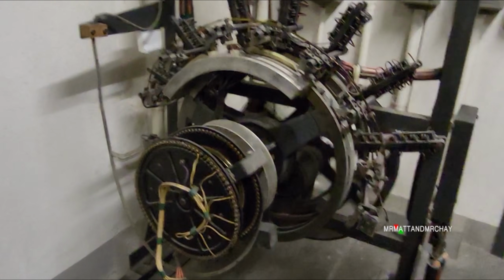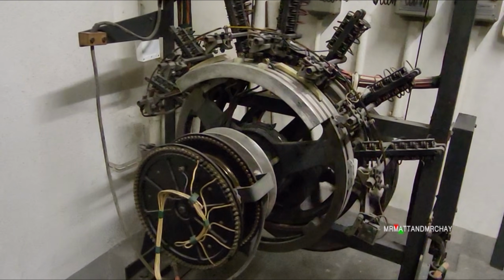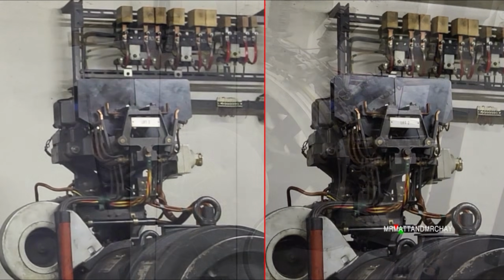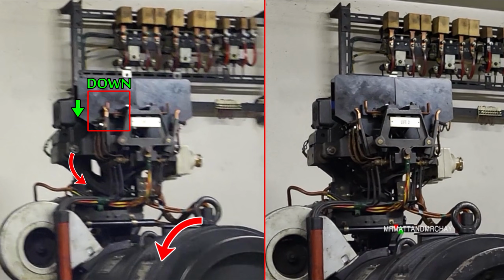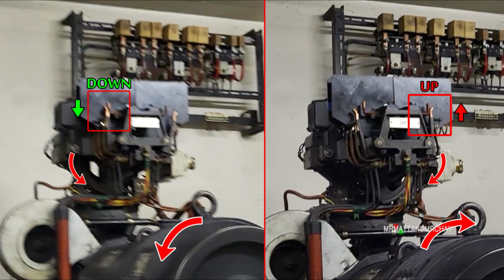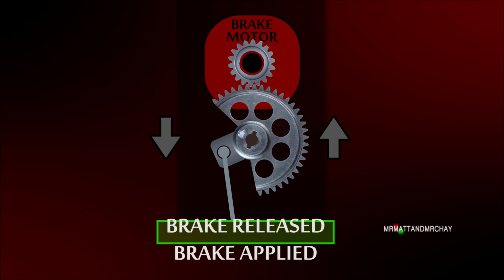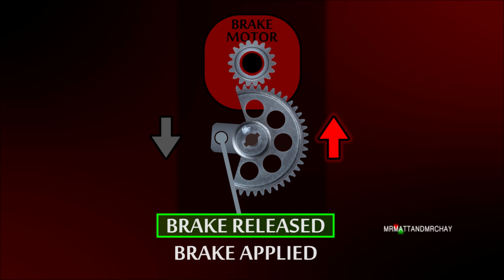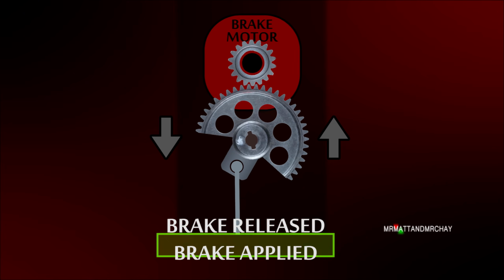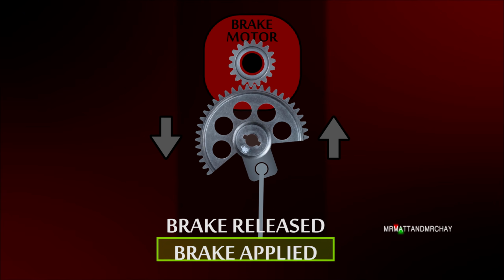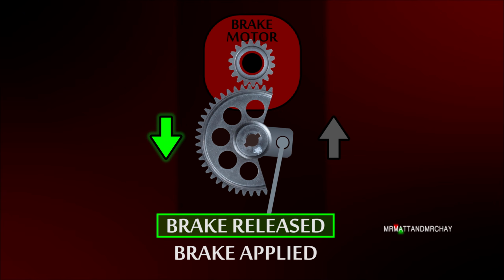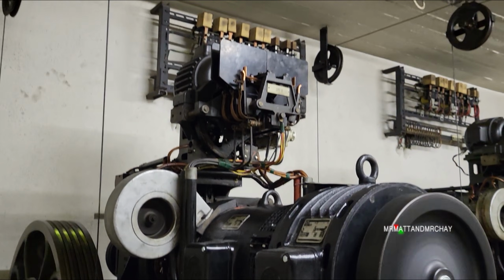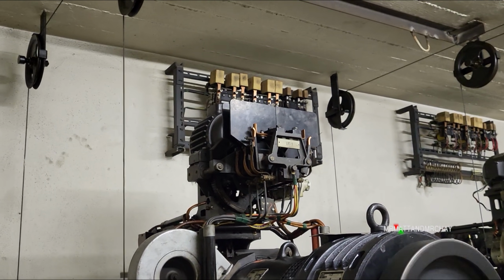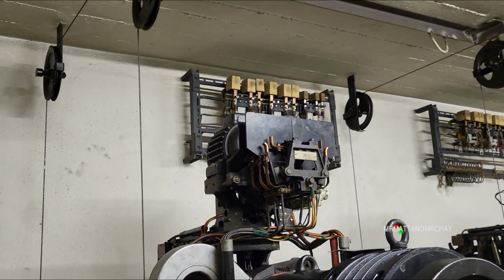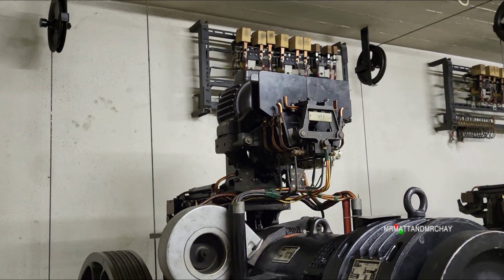The floor selector decides which direction the lift needs to go, which then commands the brake motor to turn anti-clockwise for down and clockwise for up. Whichever way it rotates, this releases the brake. But it's the contacts on the left or the right side that feed the phases to the main motor to control its direction. There is also a mechanical linkage between the left and right contacts here, making it impossible for both to be on at the same time.